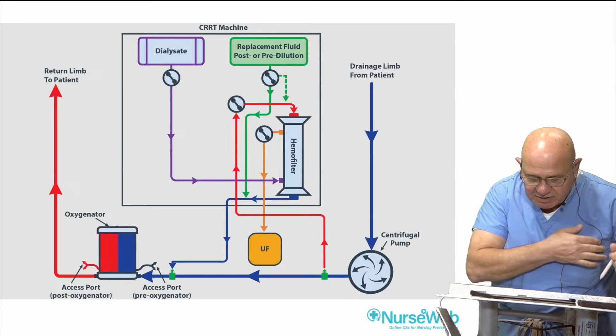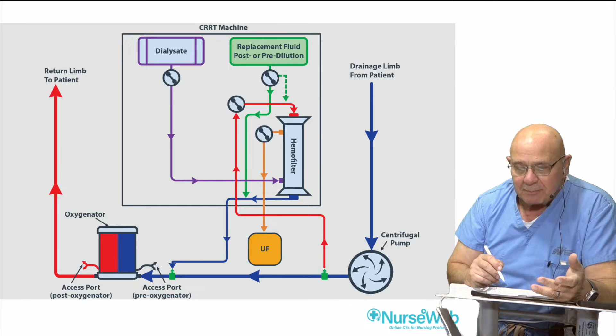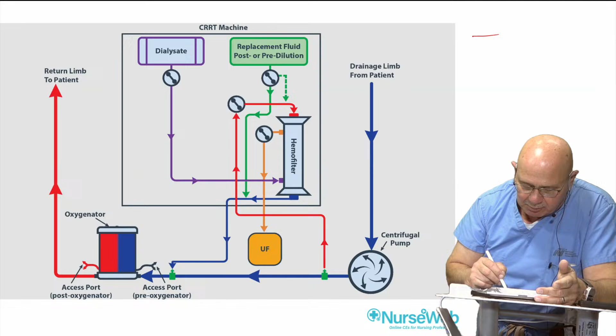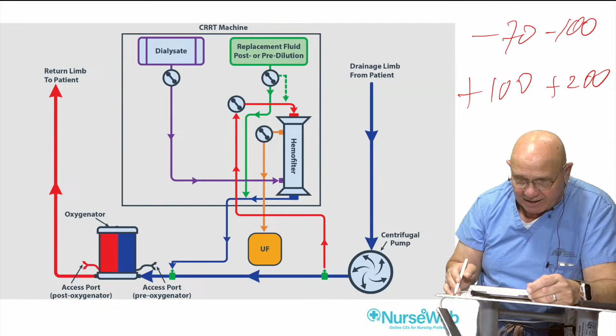Here is another way to do it. You have your access coming here from the positive side of the pump, going in, and you're returning it back to the positive side with this blood pump. Very challenging to do. It can be done, but basically these machines are designed to see certain pressures. Usually your access pressure is going to be negative, not positive. So if you're thinking about this circuit in a temporary dialysis catheter, your access is probably going to be somewhere around -70 to -100. Your return pressure going into that catheter, again, is probably going to be somewhere around +100 to +200, depending on the amount of blood flow, the amount of replacement, where the replacement is located, pre-filter, post-filter. All of those things are going to have an effect on it, the size of which catheter you use, and so forth.